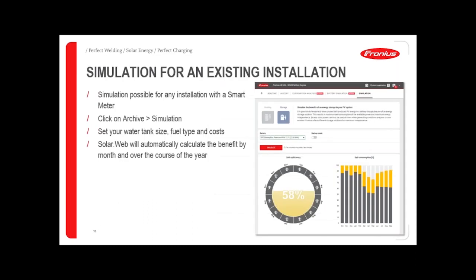A very nice new feature we have is the simulation tool. So if you have the PV system installed without a battery, what you can do is run the system for a period of time, get some data on what you're importing and exporting, and then simulate the installation of a battery. The system will actually calculate how much import and export is possible for your system and work out the additional saving and the improvement to your self-consumption if you install the battery system. That's shown here by the gold bars showing the improvement in self-consumption. You can do this for a variety of different battery sizes and model that improvement.